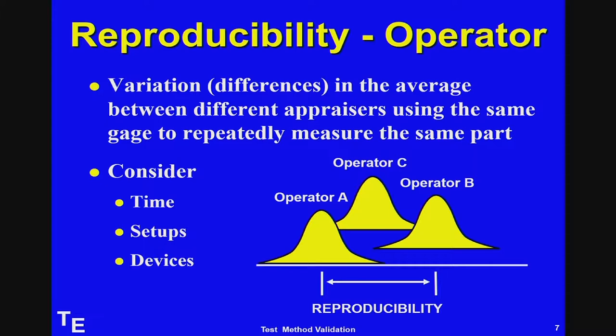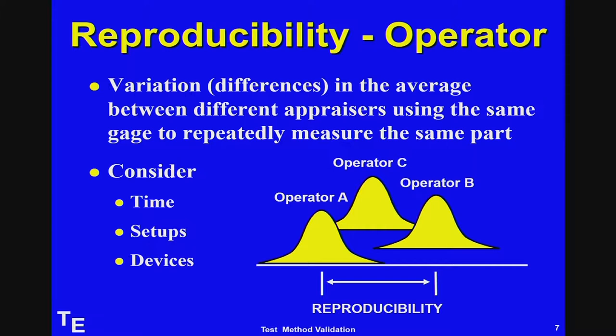When you read about gauge R&R studies, they often discuss reproducibility with respect to operators. But what if the instrument is fully automated and the operator just pushes a button? Then maybe reproducibility should be with respect to days, assays, or calibration — so reproducibility with respect to calibration curves, recalibrating on three different days, maybe with three different operators. Reproducibility should be defined relative to whatever makes the most sense for your measurement device.